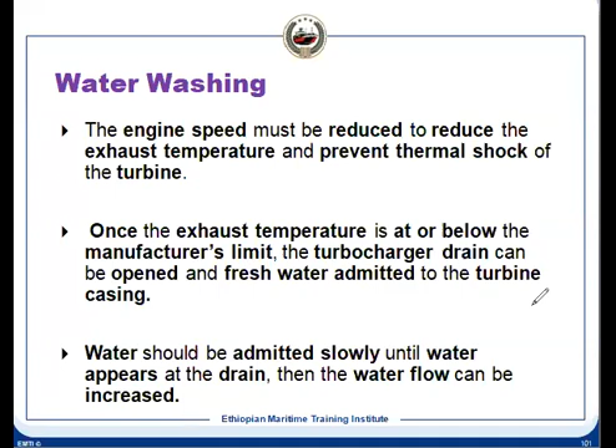Then we monitor the drain, the condition of the water coming out from the turbine. Once the drain water you see is clear, it means your cleaning is completed. It takes around 10 to 15 minutes. If you do the regular washing on time, you will see clear water coming out in 10 to 15 minutes. Once the water is coming out clear, you shut off the water supply. After that, you keep the drain open, because there is still water inside that will come out. Once that stops coming, you increase the speed of the turbine. After that, you close the drain. So the water washing of the turbine is completed, and it is usually done on a weekly basis. For the compressor washing, it is done every day or alternate day, around 24 hours or 48 hours.